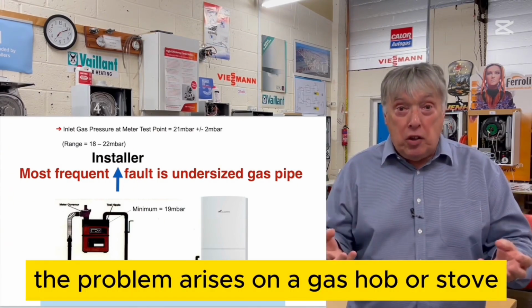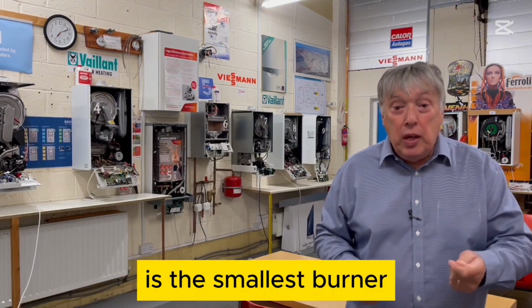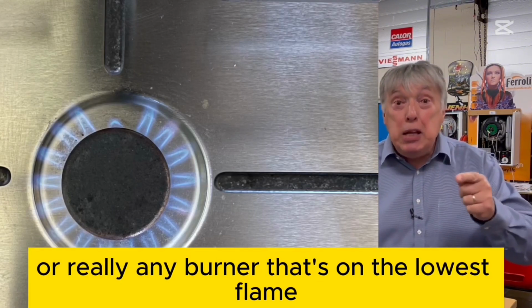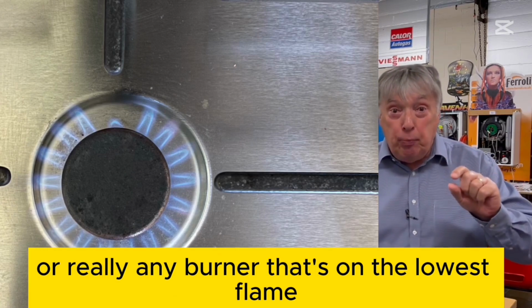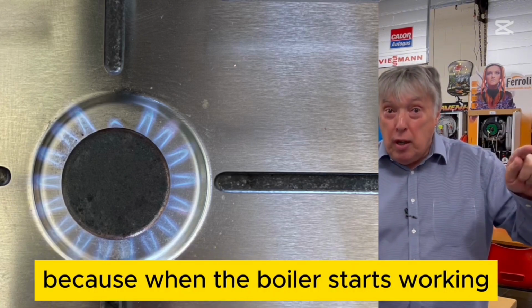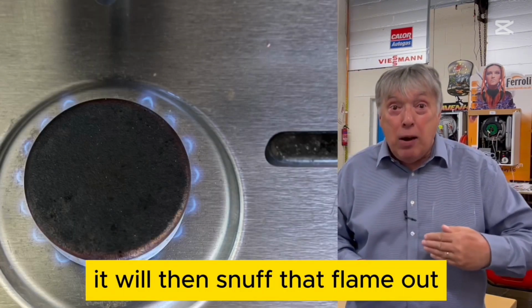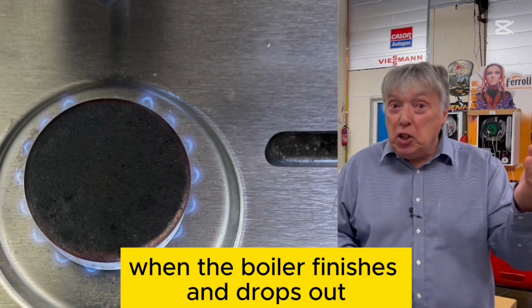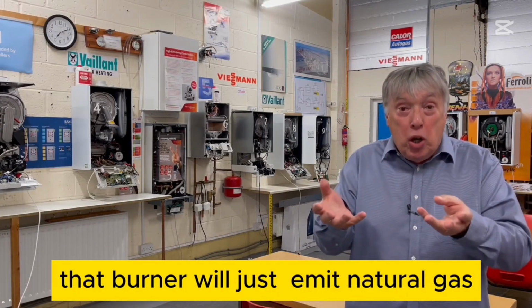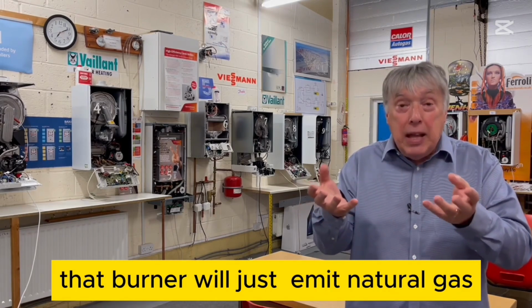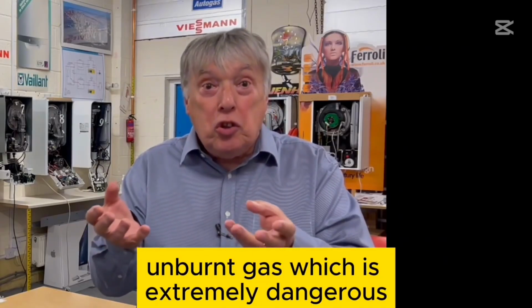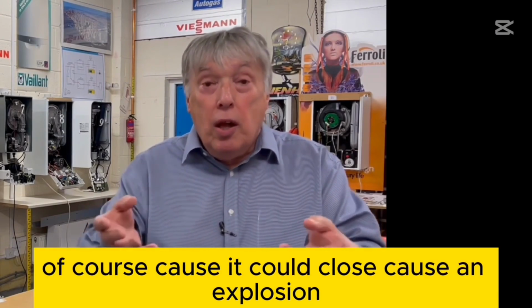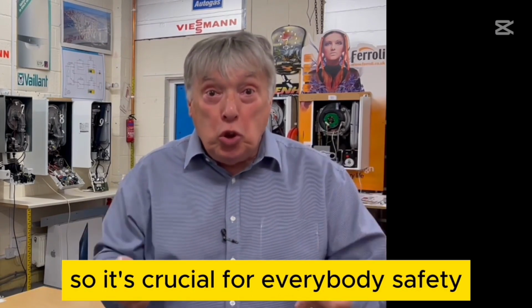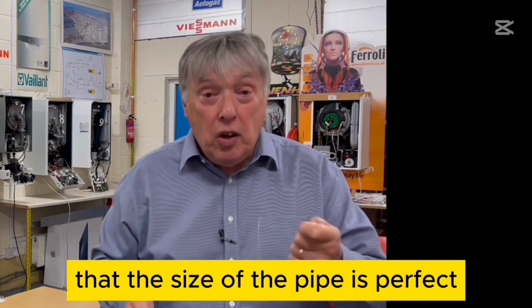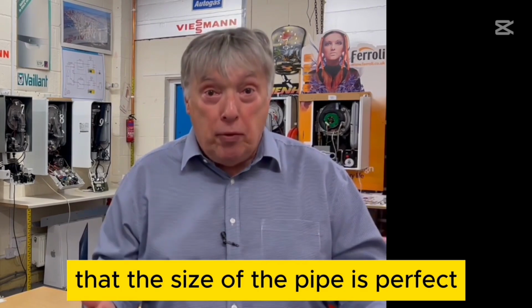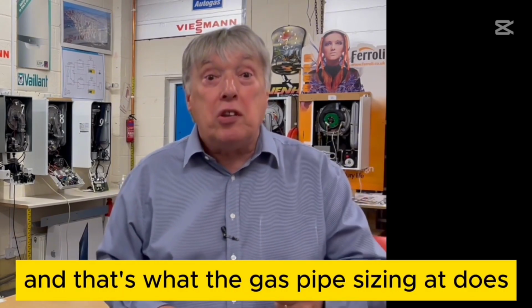The problem arises on a gas hob or stove. It's the smallest burner, or really any burner that's on the lowest flame, because when the boiler starts working, it will then snuff that flame out. When the boiler finishes and drops out, that burner will just emit natural gas, unburnt gas, which is extremely dangerous, of course, because it could cause an explosion. So it's crucial for everybody's safety that the size of the pipe is perfect. And that's what the gas pipe sizing app does.